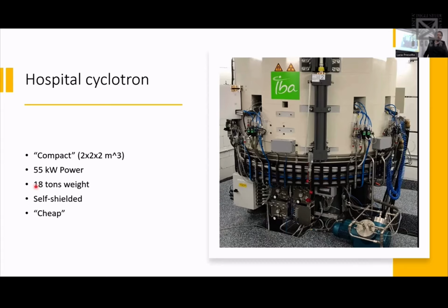It just uses 55 kilowatts of electrical power. It weighs 20 tons. It's self-shielded. So probably half of the weight is water, paraffin, and lead to shield the different kinds of radiation that come out of that. And it's, by the way, relatively cheap. It's like 1 or 2 million euros. It will last 20, 30 years.